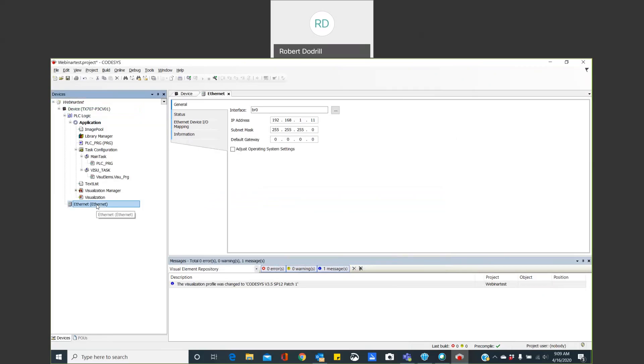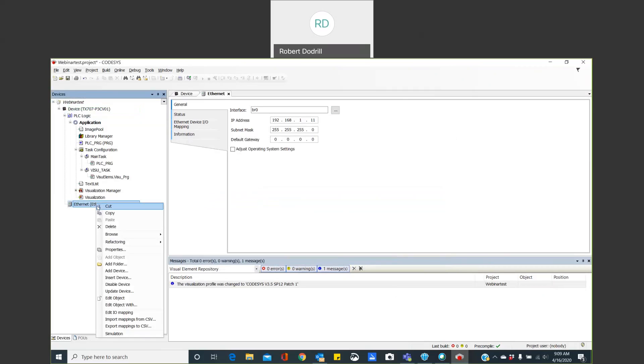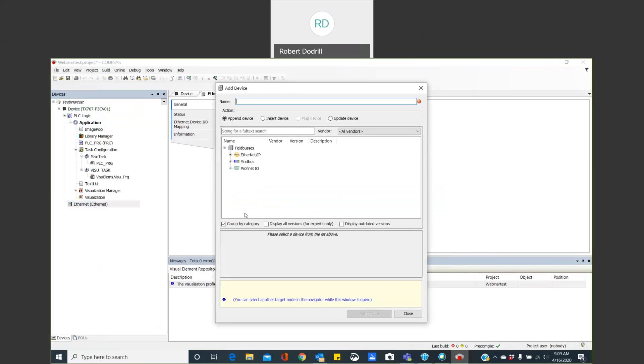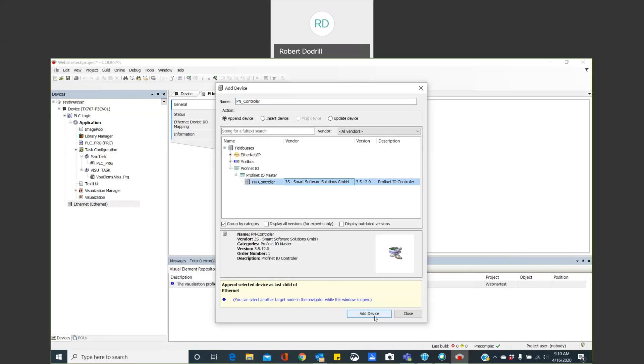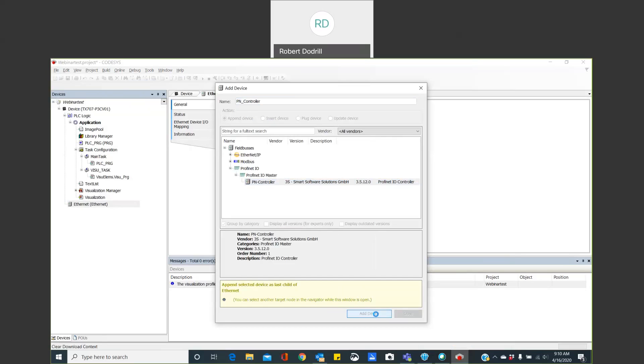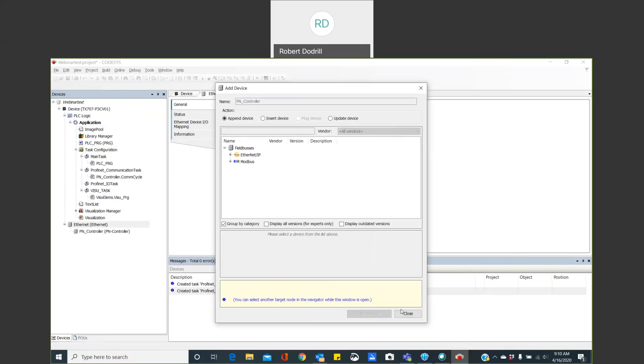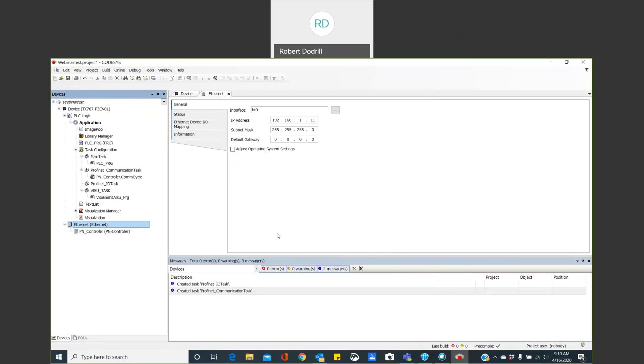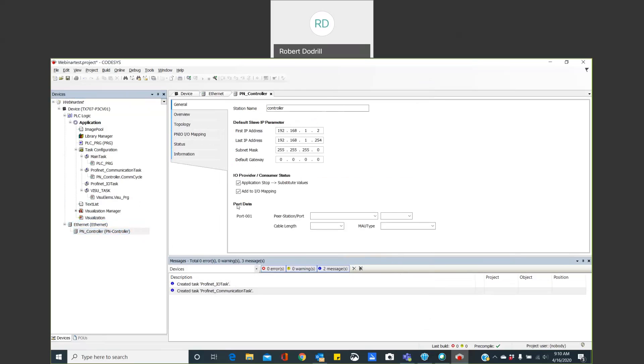In my case, my next step is that I want to right click on Ethernet. I want to add device again. Now, I am choosing to use Profinet as my communication protocol. I just personally like Profinet. If you like Ethernet IP, here's your driver. If you like Modbus TCP, here's your driver. In my case, I'm going to add Profinet to my project. And again, I'm going to close this. Now, I want to go to my Profinet device. And notice, since I already have a connection, since I've already set up my Ethernet, it goes ahead and loads the basic parameters that says OK, you can use anything between 1.2 and 1.254. So this is already set up for me. So my next step's kind of cool.